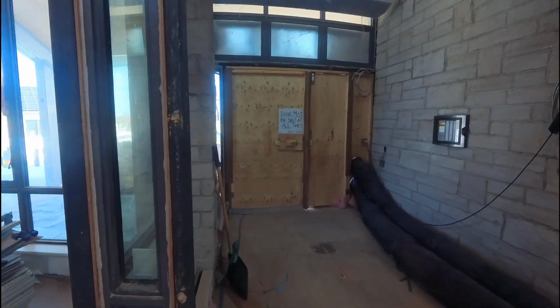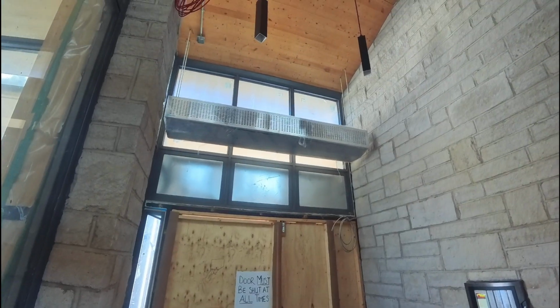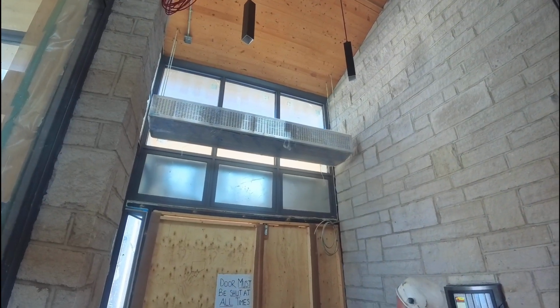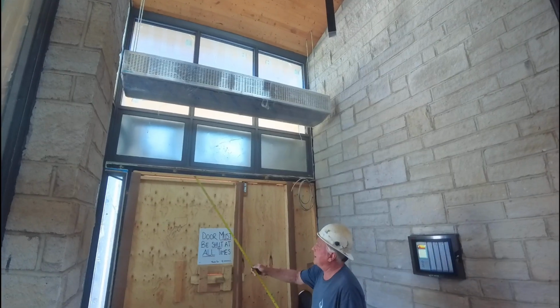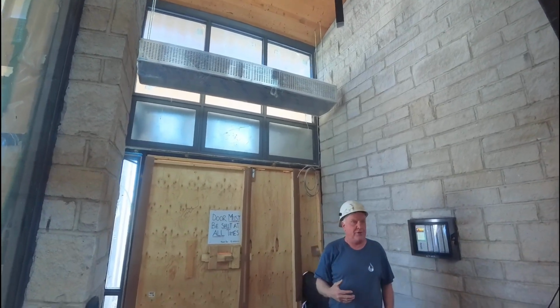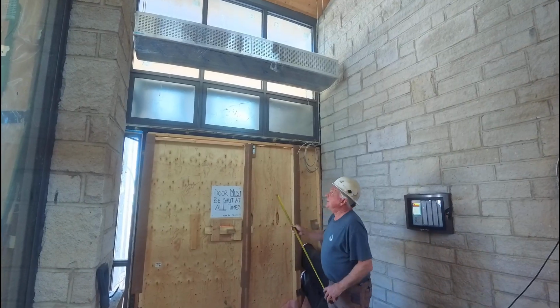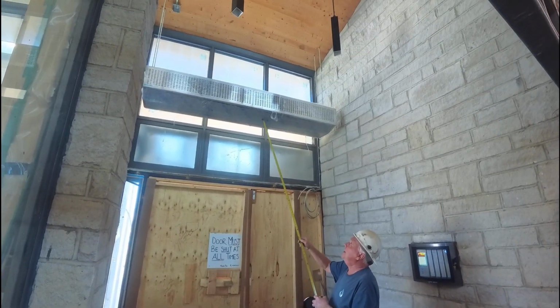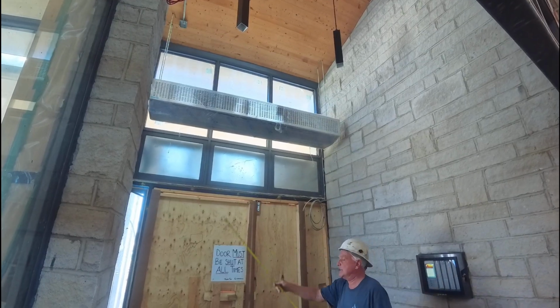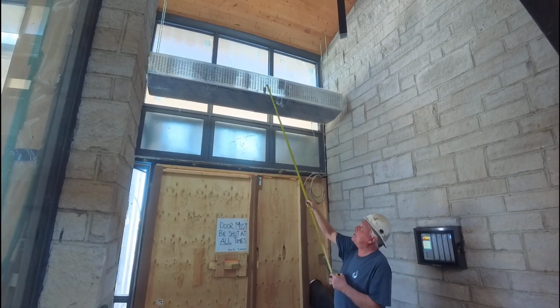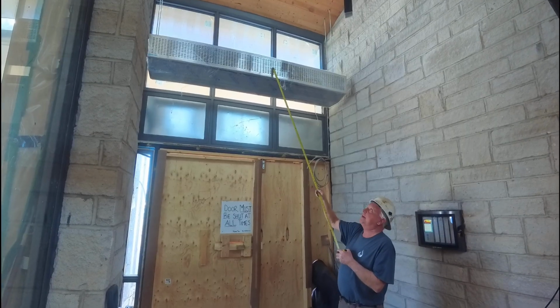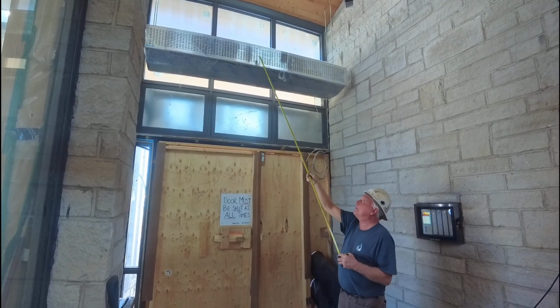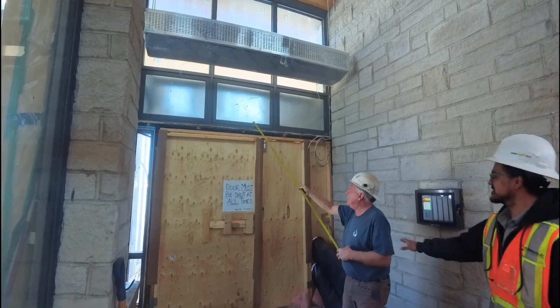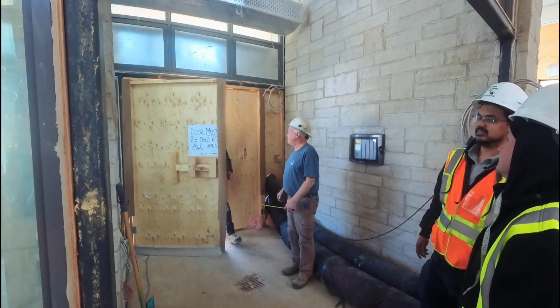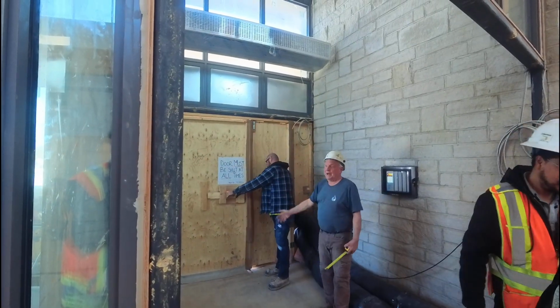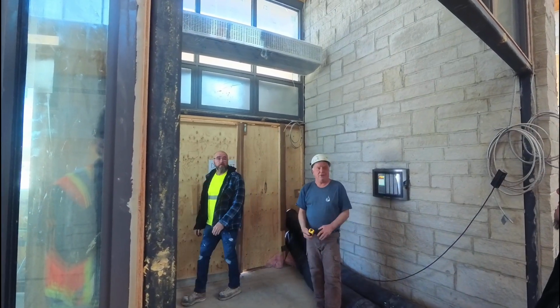I'll be here for, this is something we just hung last week there. It's commonly referred to as an air curtain. Normally they're used to give a person a blast of warm air when they walk into a building from the cold outside. This one's got a little different use to it. It's going to heat this entire vestibule area. The return air is going to be pulled in through this end up here, all that hot air up there will get recycled, and now it'll be blown straight down, and it'll just be a big circle, and that'll cover everything.